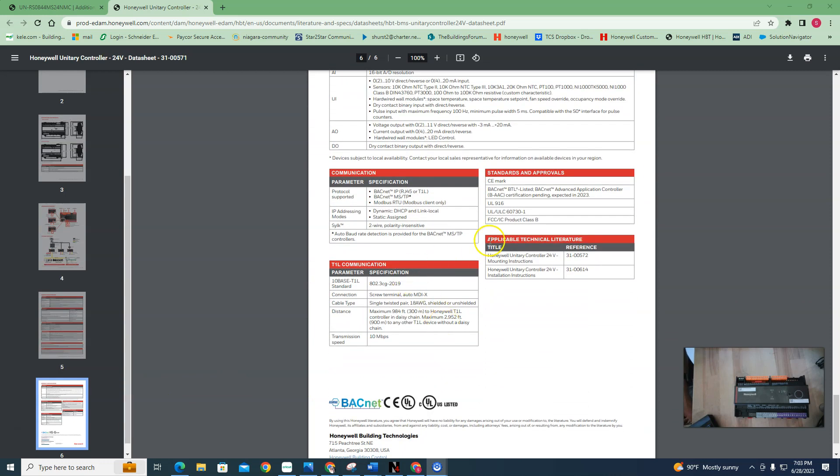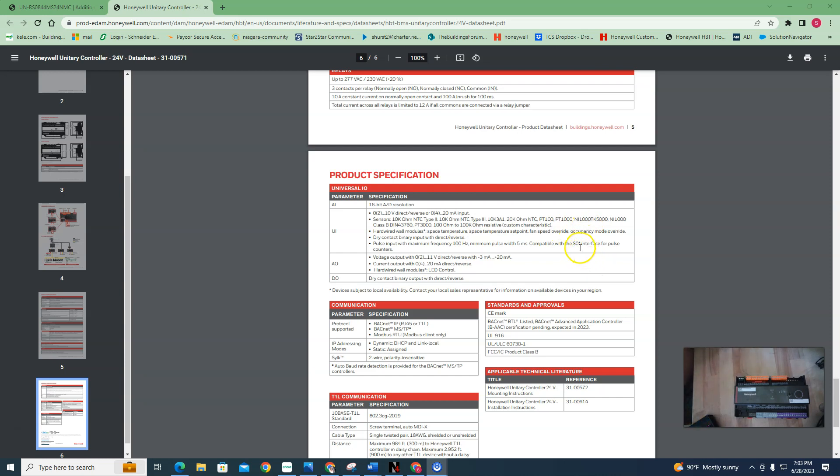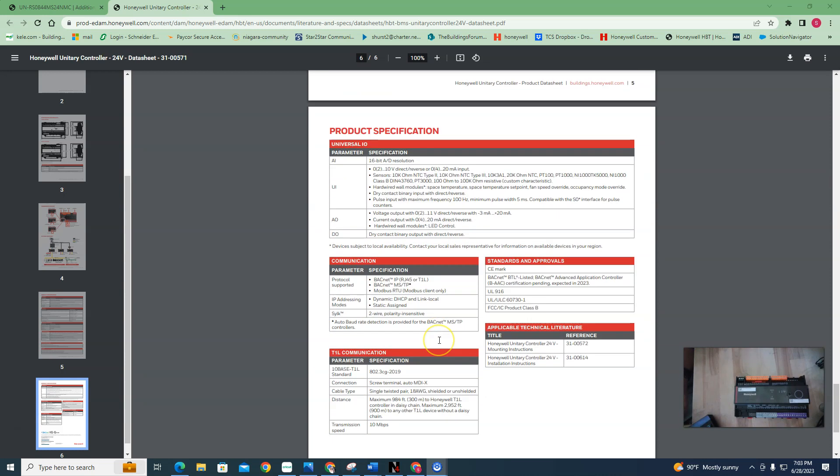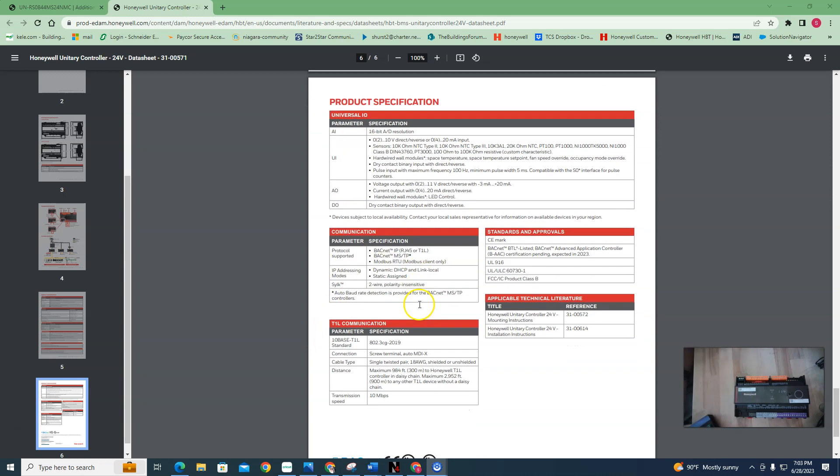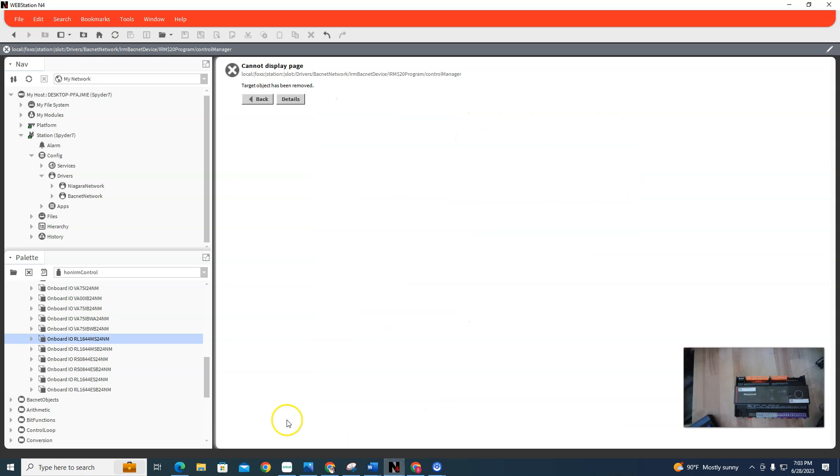The price point is really good. I can't talk about pricing because everybody's multiplier is different, but the price point on this is really really good. And sensors - you're not limited to 10k and 20k anymore with Honeywell. Here's all the different sensor types that you can have. If you're taking over a Johnson building, you can put in this nickel 1k right there because most Johnson buildings are nickel 1k. Platinum 1k, you know, so you're not having to replace every single sensor. It's especially good as a plant controller for that.